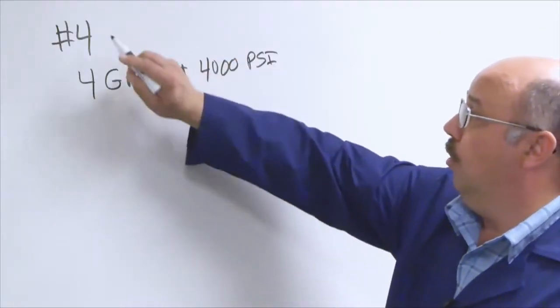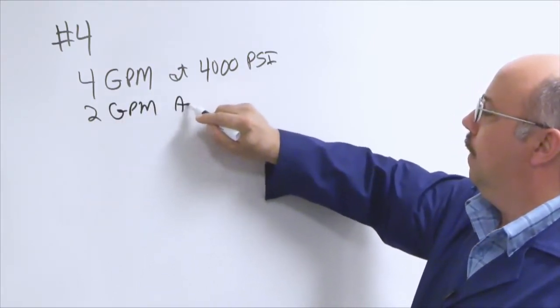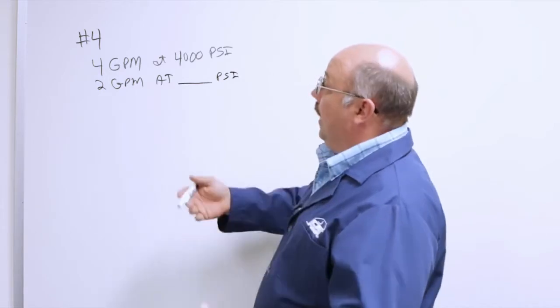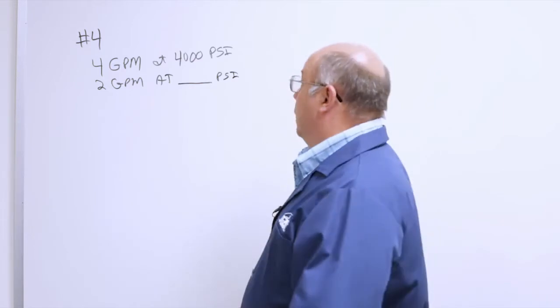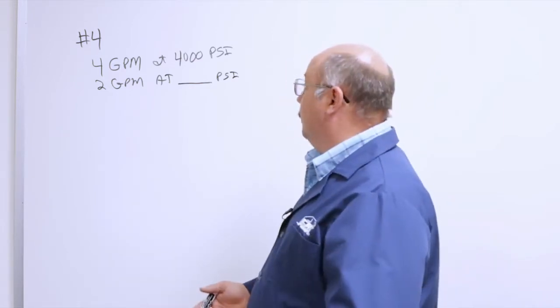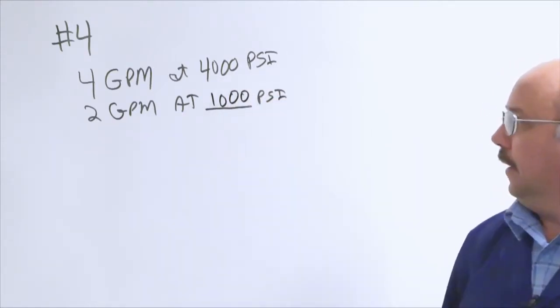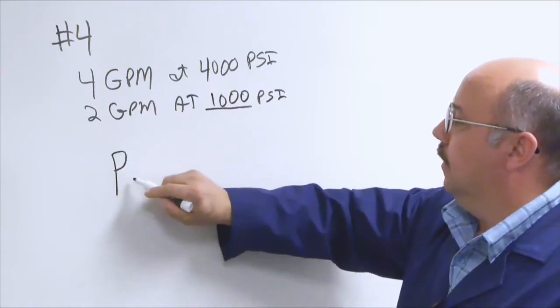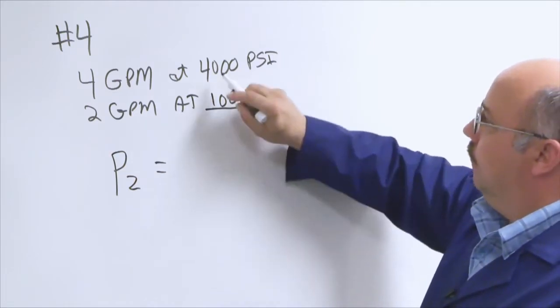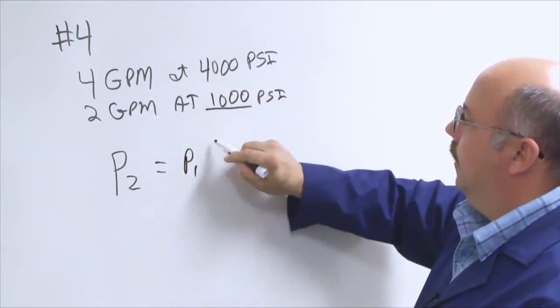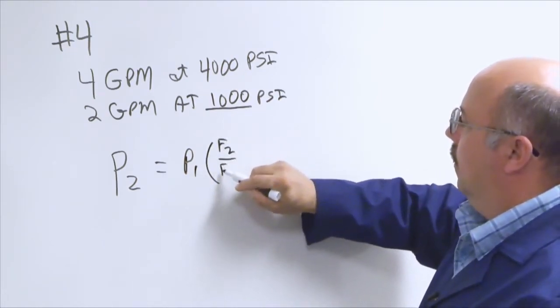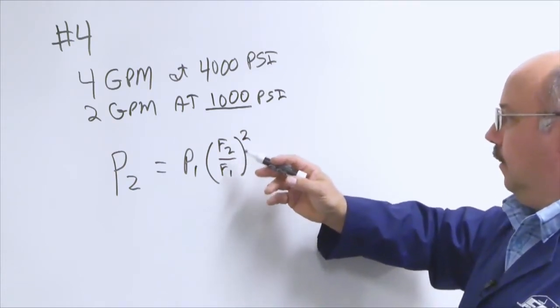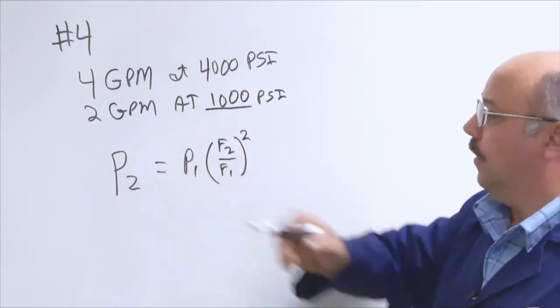If I were to drop the flow on a number four nozzle to two GPM, what pressure would we have? One wants to think it would be 2,000 psi because we got half the flow, we get half the pressure. Well, that's not true because it's a squared function the way water goes through the nozzle and has a pressure drop. The right answer is 1,000 psi. The formula is: P2 equals P1 times the ratio F2 over F1, and then this is squared. If we throw the numbers in, we get 4 over 2, which is 2. Square that, we get 4. 4 times 1,000 is 4,000. So the formula works out, and we can use this to calculate what flow we need in a system.